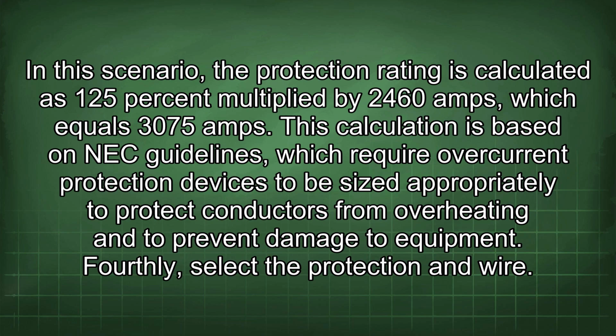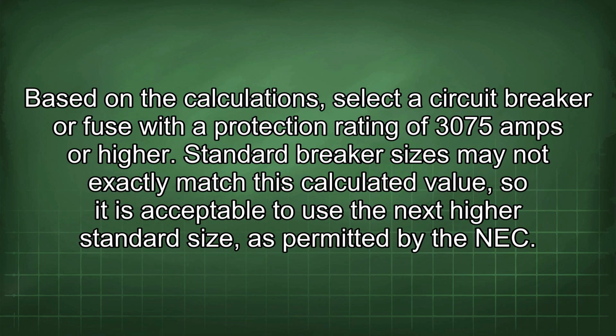This calculation is based on NEC guidelines, which require overcurrent protection devices to be sized appropriately to protect conductors from overheating and to prevent damage to equipment. Fourthly, select the protection and wire. Based on the calculations, select a circuit breaker or fuse with a protection rating of 3075 amps or higher. Standard breaker sizes may not exactly match this calculated value, so it is acceptable to use the next higher standard size, as permitted by the NEC.